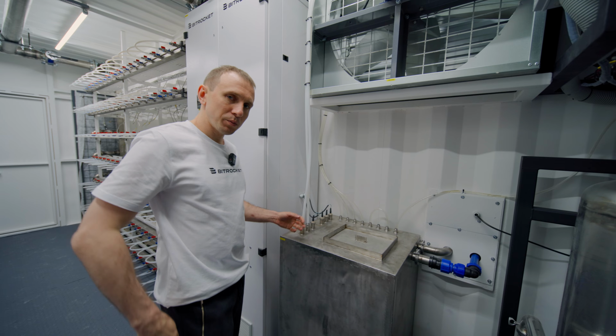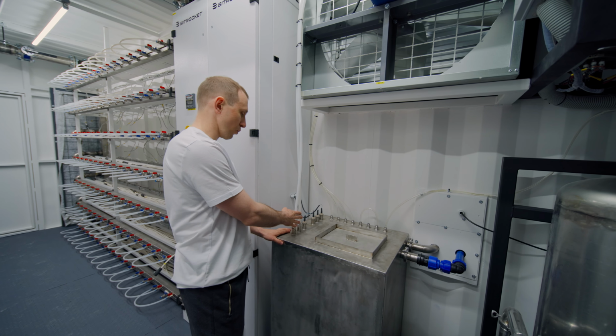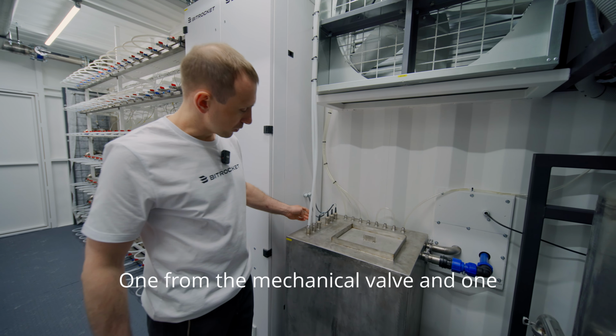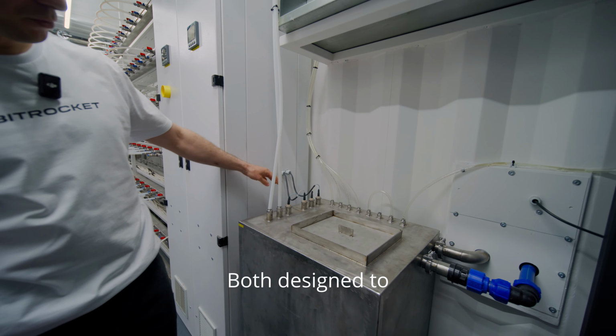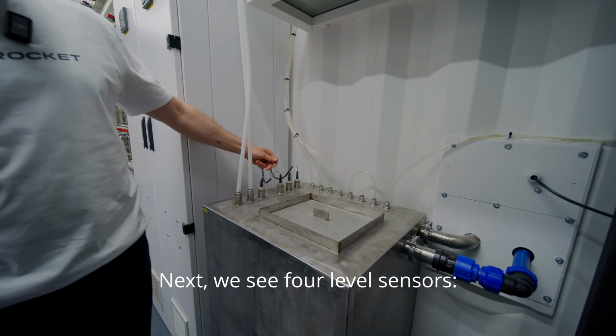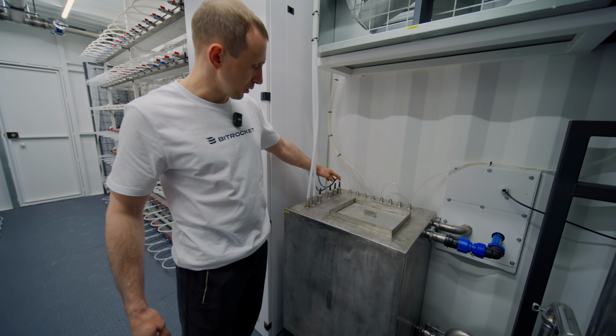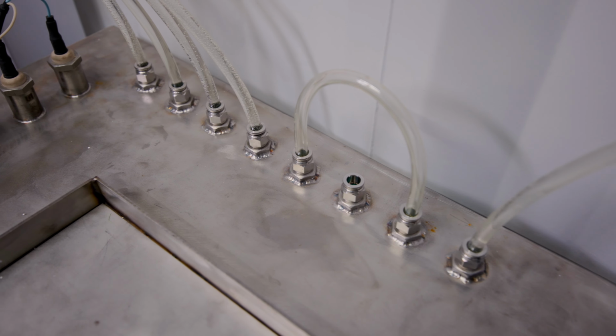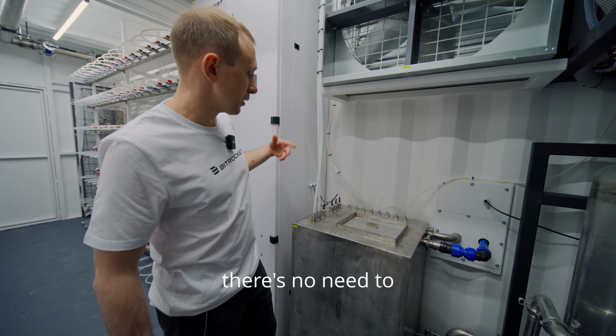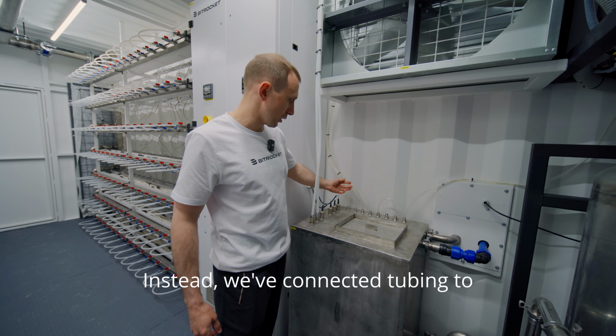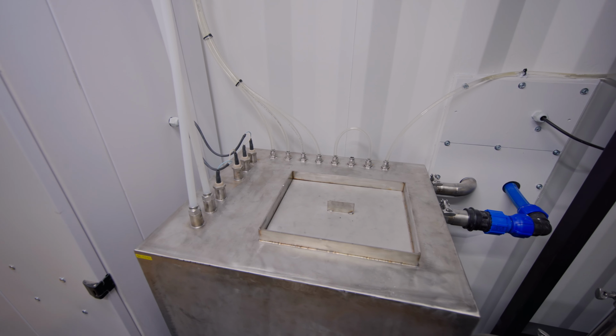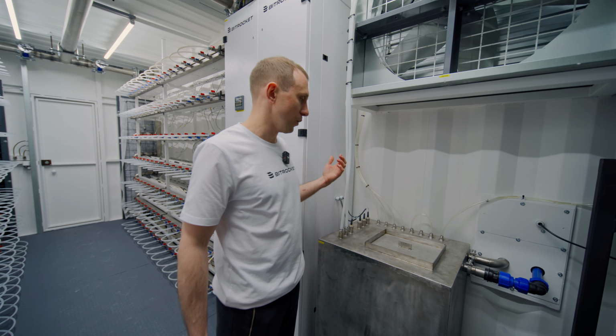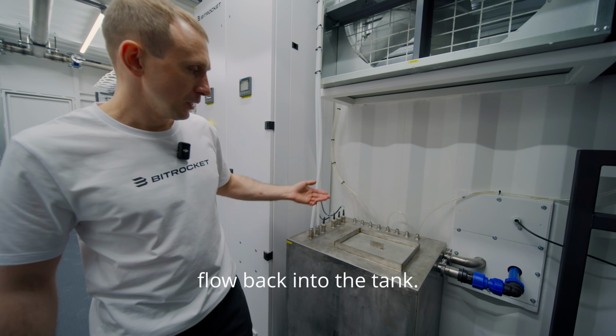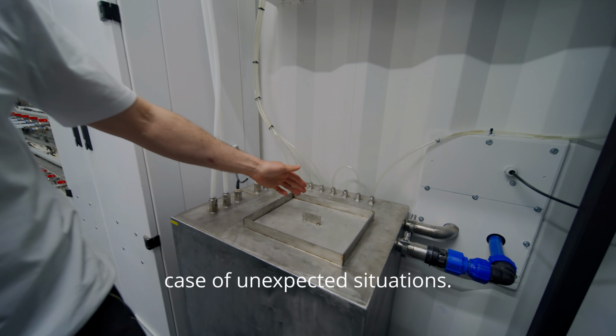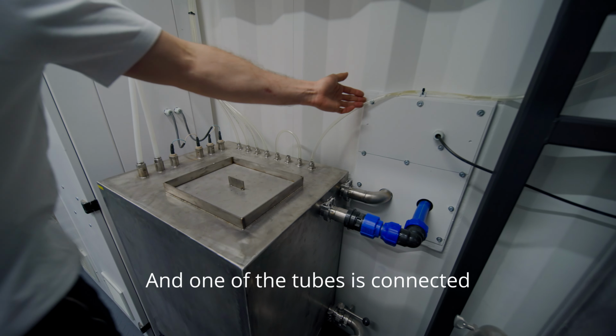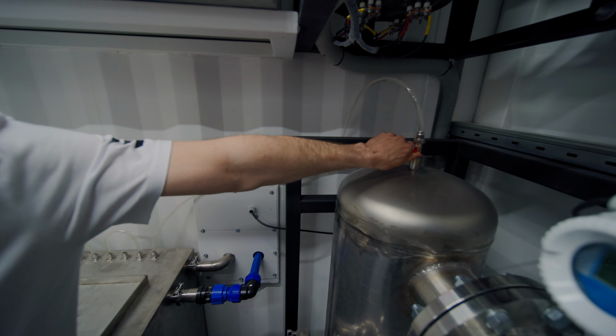Let's add some information about the top-up tank. Two emergency overflow lines enter here, one from the mechanical valve and one from the electric one, both designed to maintain safe system pressure. Next, we see four level sensors: base, minimum, normal, and maximum. The next four pipes come from vertical manifolds. These collect air. This way, when you're filling the system, there's no need to stand around with buckets. Instead, we've connected tubing to standard air vents, linked via compression fittings. So, you slightly open all four valves, start filling the system, and the air bubbles automatically flow back into the tank. There are also several reserve ports in case of unexpected situations, and one of the tubes is connected directly to the de-aerator. Let's open the valve.